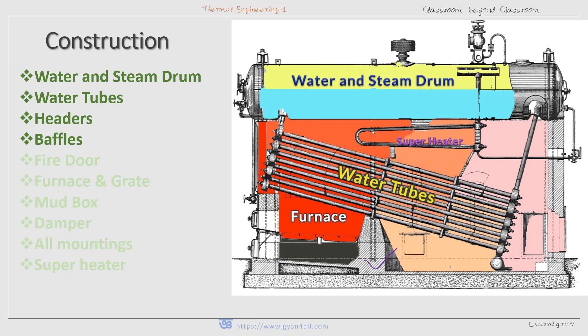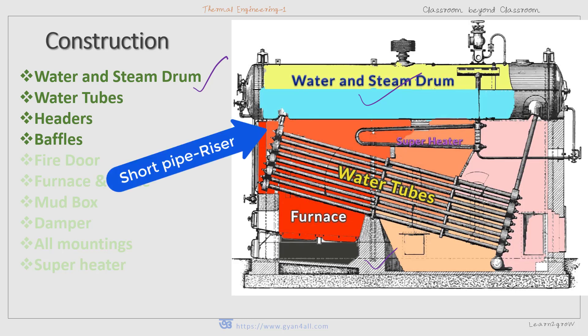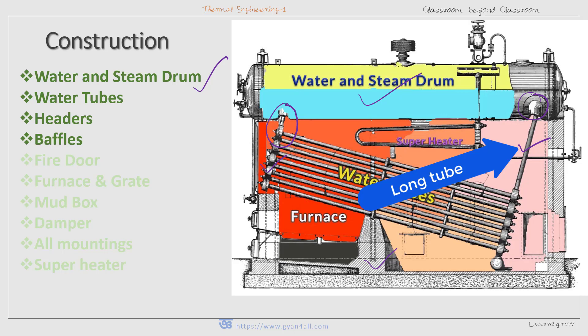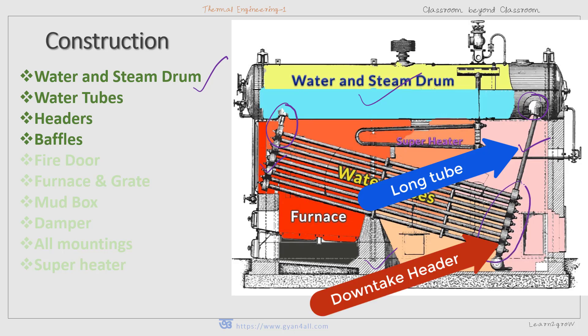The steam and water drum is one of the important parts of the Babcock and Wilcox boiler. It is a horizontal axis drum containing water and steam, and about half of the drum should be occupied by steam. Below the drum there is a short tube connected to the uptake header, also called the riser. There is also a long tube which connects the steam drum to the downtake header.